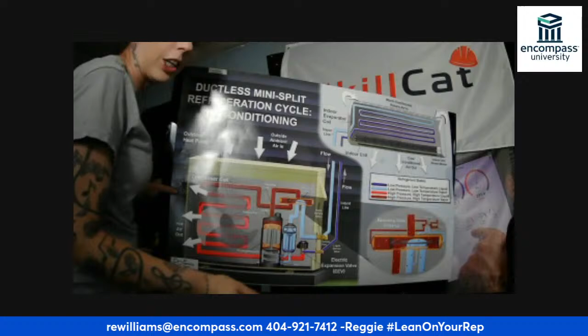And it doesn't matter what unit you're on. That's not just mini splits. No AC compressor sees liquid. If it sees liquid, it will what we call slug, and it will eventually copper plate and it will die. So we come in as a vapor and we leave as a vapor on the discharge line.